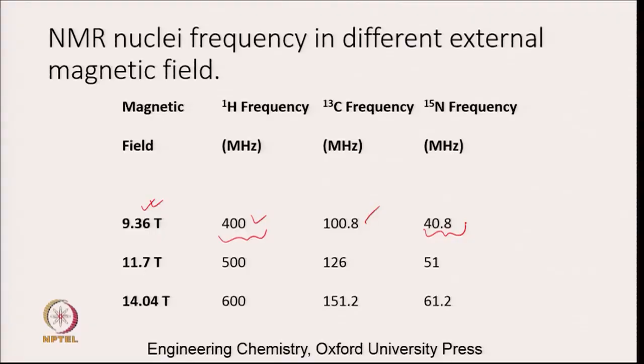On a 400 MHz machine the ¹³C frequency will be 100.8 MHz, whereas the ¹⁵N frequency will be 40.8 MHz. This is on a machine with magnetic field 9.36 tesla. If you change the magnetic field to 11.7 tesla, then your frequency is 500 MHz for proton, 126 MHz for ¹³C, and 51 MHz for ¹⁵N. On a 14.04 tesla spectrometer you have a proton frequency of around 600 MHz, ¹³C frequency of around 151.2 MHz, and ¹⁵N frequency of around 61.2 MHz.